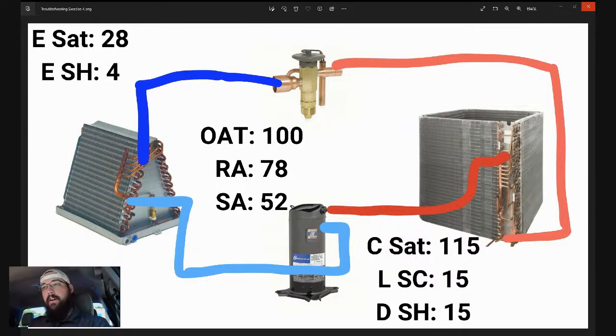So our outside air is 100 degrees. Return air in the space is 78. We have a supply air of 52. This is just a regular split system, nothing fancy going on here. We have an evaporator saturation of 28, evaporator superheat of 4, a condenser saturation of 115, liquid line subcooling of 15, and a discharge superheat of 15. So I see one for airflow.